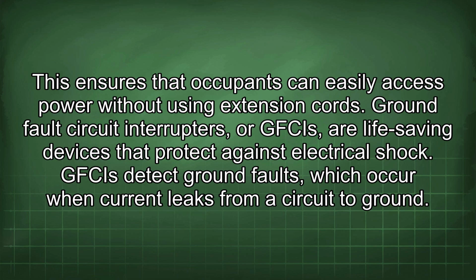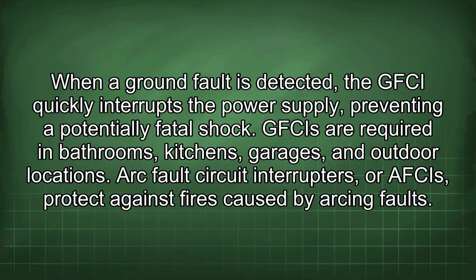Ground fault circuit interrupters, or GFCIs, are life-saving devices that protect against electrical shock. GFCIs detect ground faults, which occur when current leaks from a circuit to ground. When a ground fault is detected, the GFCI quickly interrupts the power supply, preventing a potentially fatal shock. GFCIs are required in bathrooms, kitchens, garages, and outdoor locations.